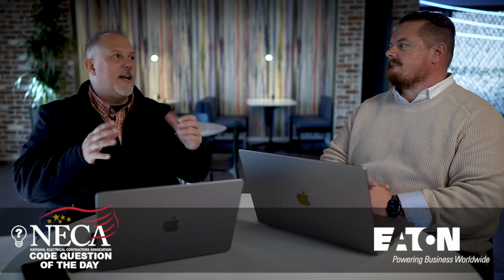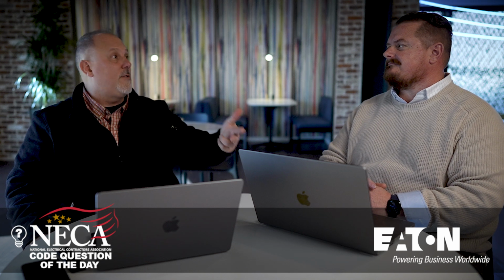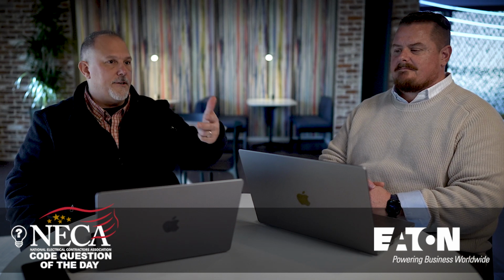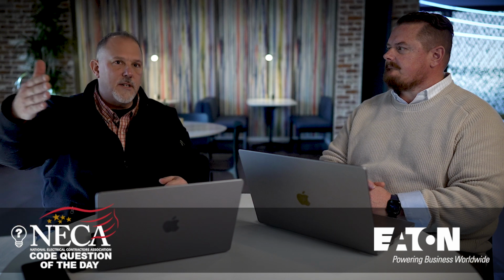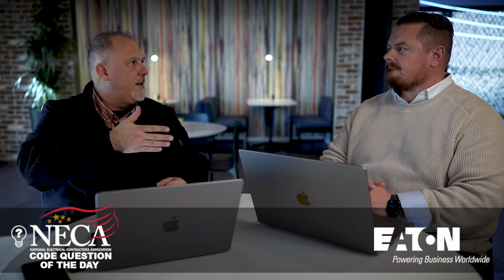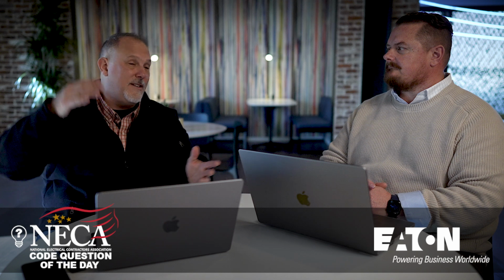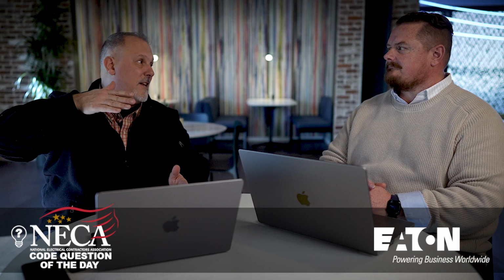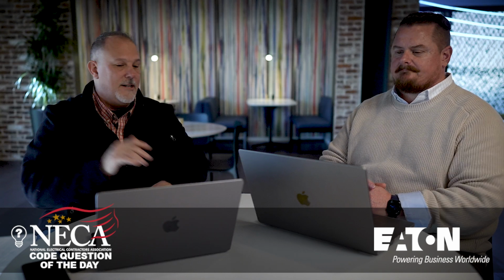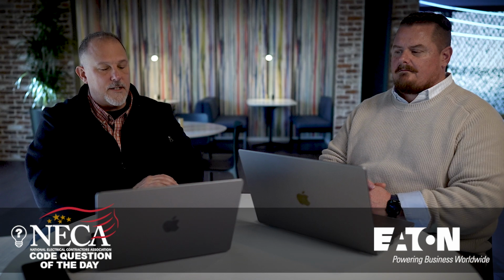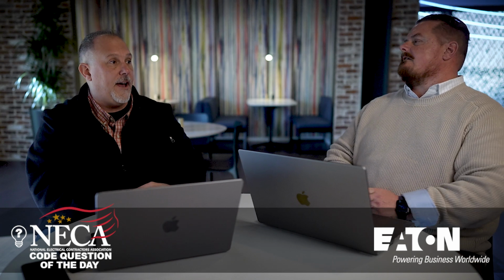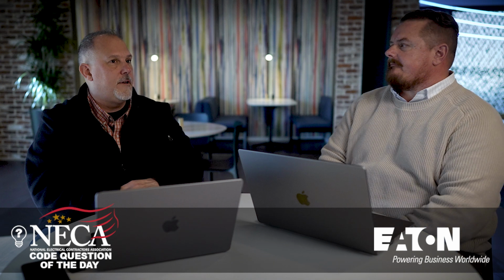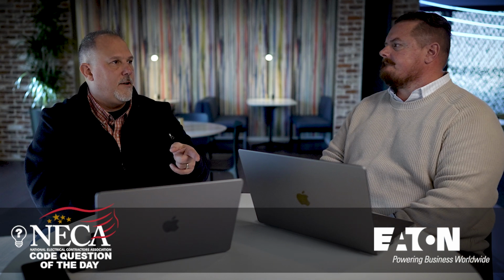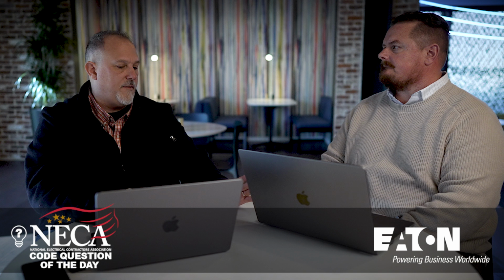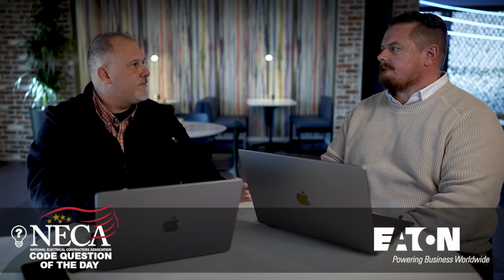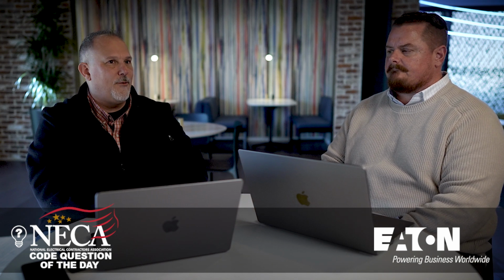So you've got to understand the recipe that you're going for, and then understand I have to do this calculation down to that equipment, but not necessarily all the way down to it. At least when I get to a low enough number, then I say, okay, I'm done. Right. Right. But that's another part of the challenges that we have: do I have enough data from what the engineer or the qualified person did when they calculated that fault current, and then work your way back down.